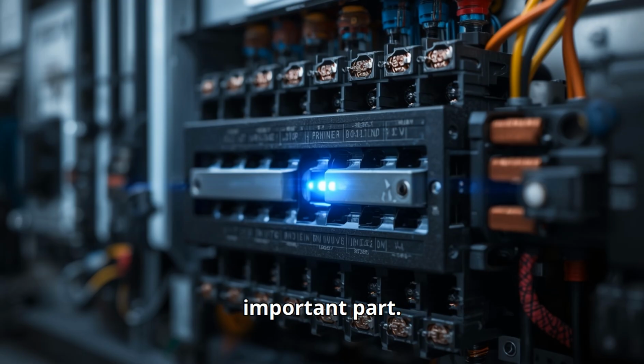Here's the important part. When electricity returns, the contactor does not close again automatically. Someone must press the start button again. This safety feature is called no voltage release, or under voltage protection. It prevents unexpected machine movement after power restoration. Such a simple design has saved countless lives around the world.